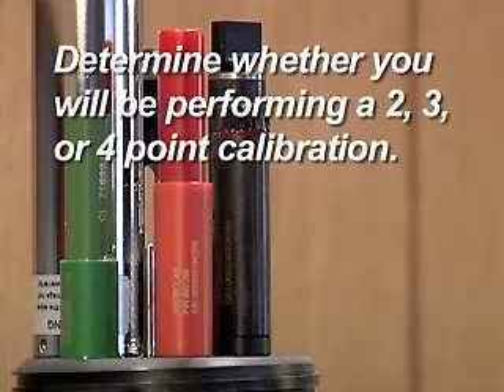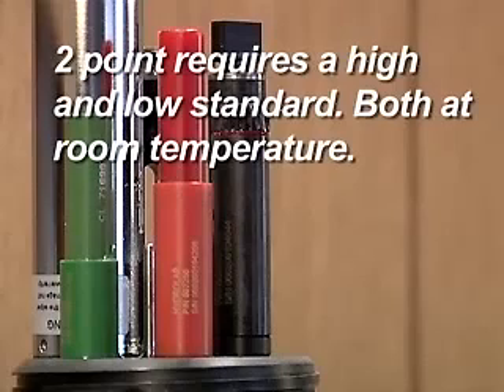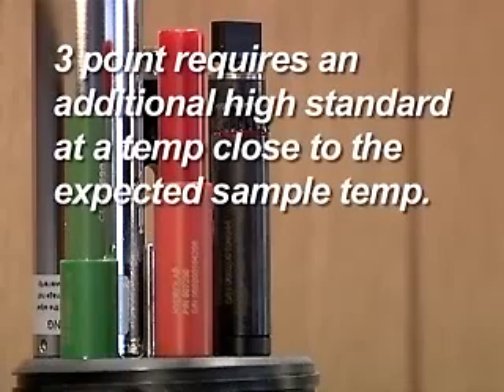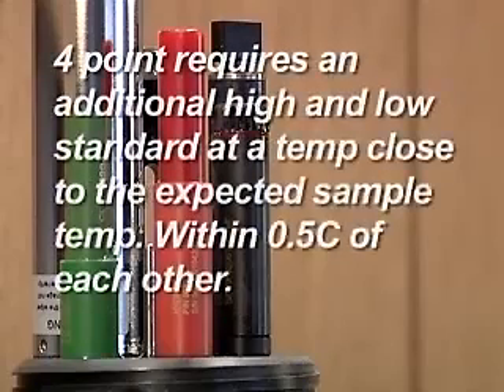Determine whether you will be performing 2, 3, or 4-point calibration. A 2-point calibration requires a high and low standard, both at room temperature. A 3-point calibration requires an additional high standard at a temperature close to the expected sample temperature. A 4-point calibration requires an additional high and low standard close to the expected sample temperature and within 0.5 centigrade of each other.